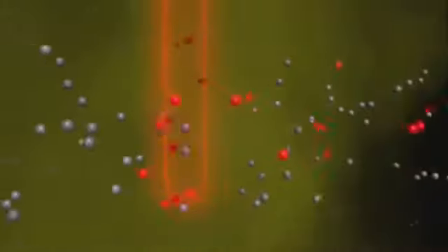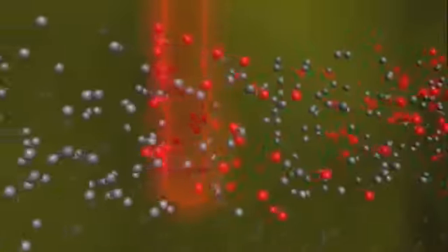But how is the heat actually transferred from the heated temperature sensor to the gas flowing past? This sequence shows that the heat is transferred by the gas molecules themselves. When the gas flows past, the molecules absorb tiny heat packets and carry them along with the flow. The faster the gas flows, the more often they absorb the heat. The heat transfer also depends on the density of the gas because at a higher pressure or lower temperature, there are more gas molecules in the pipeline. The greater number of molecules results in more contact with the heated sensor, meaning increased cooling and thus increased heating current flow.